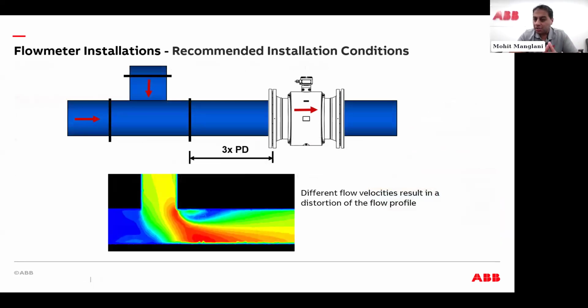So, installations around bends, this comes up a lot. I don't have any upstream diameters. I need to install the meter right next to a bend. You can look at this picture. This shows the velocity profile of what flow looks like coming around a bend. You can see that's far from laminar.